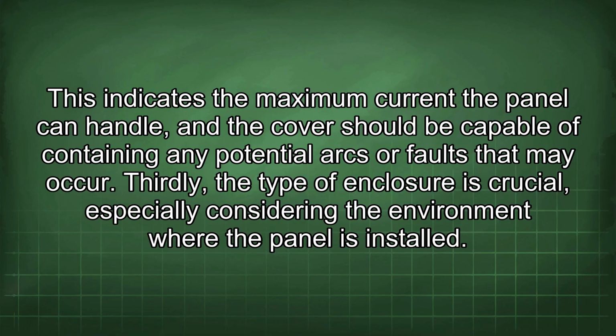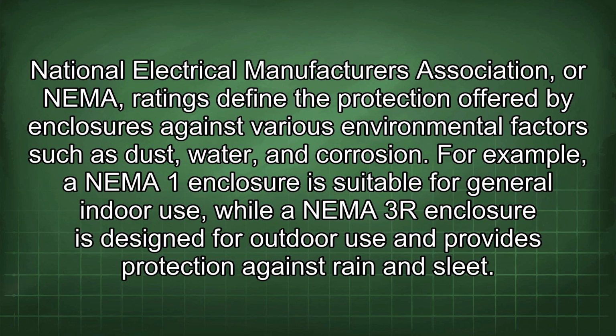Thirdly, the type of enclosure is crucial, especially considering the environment where the panel is installed. National Electrical Manufacturers Association, or NEMA, ratings define the protection offered by enclosures against various environmental factors such as dust, water, and corrosion. For example, a NEMA 1 enclosure is suitable for general indoor use, while a NEMA 3R enclosure is designed for outdoor use and provides protection against rain and sleet.